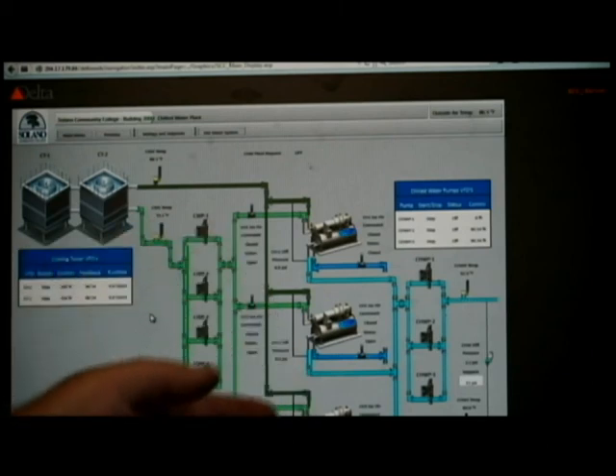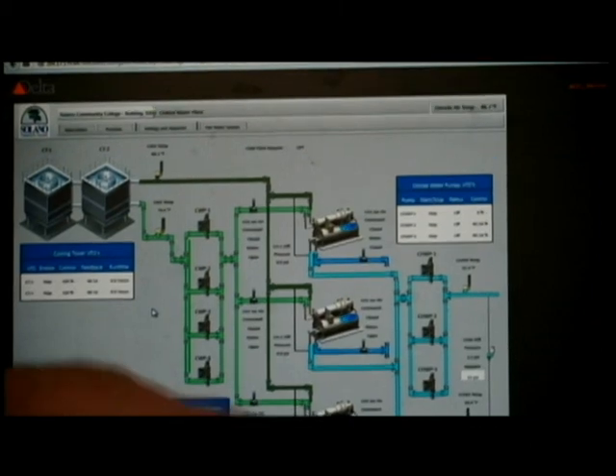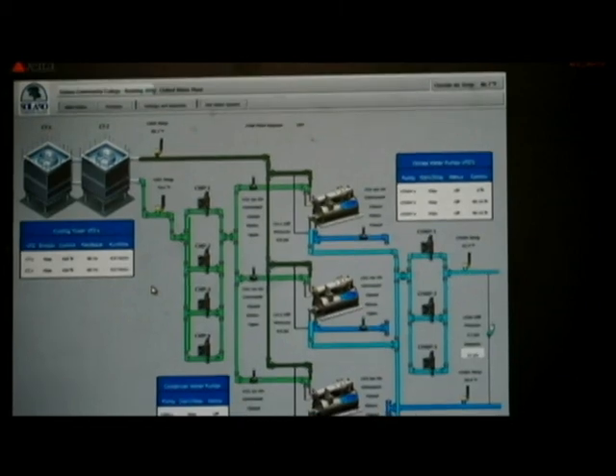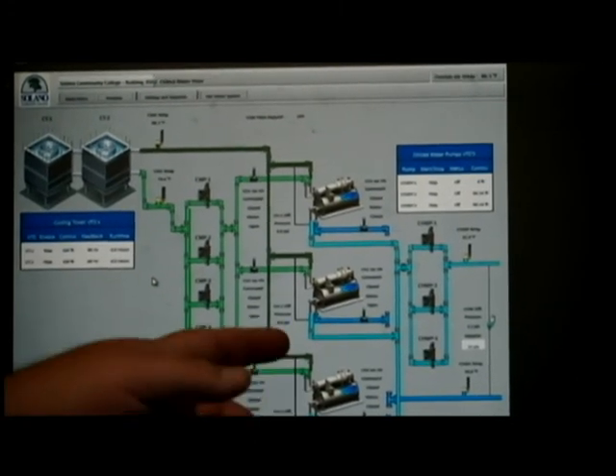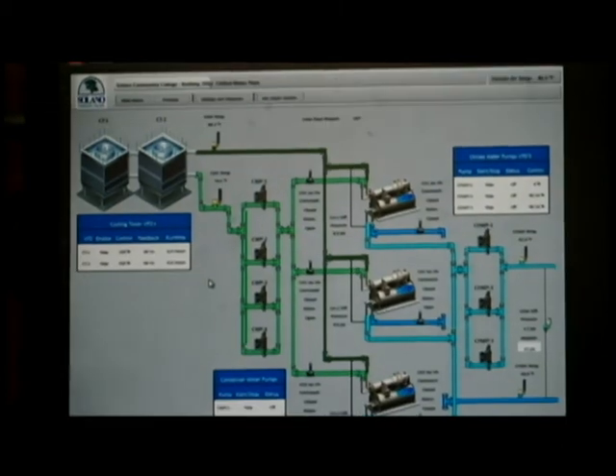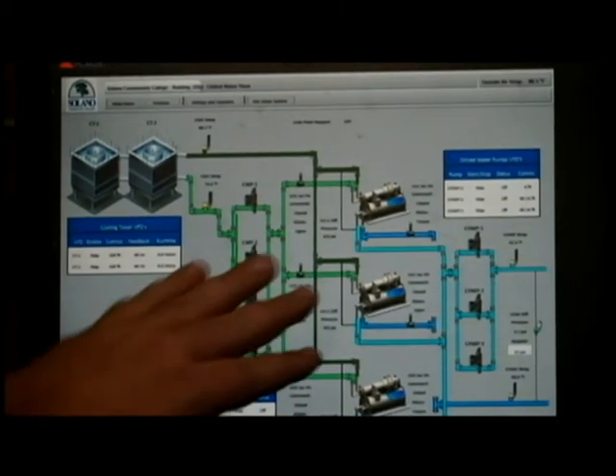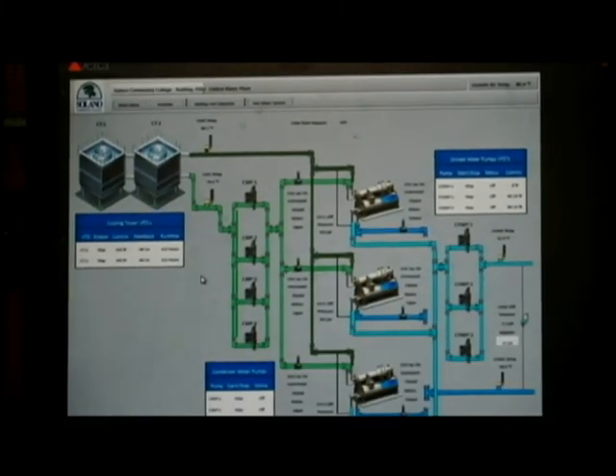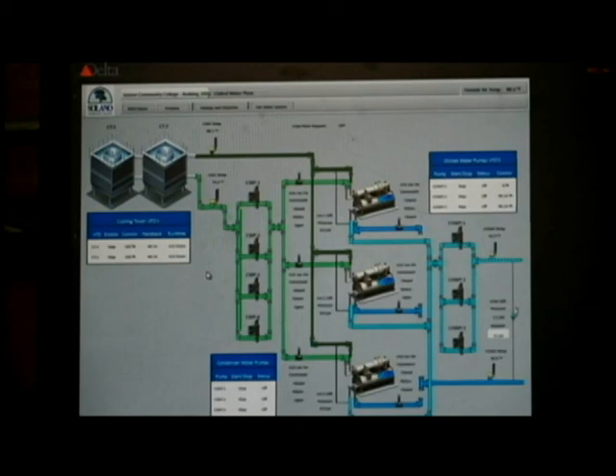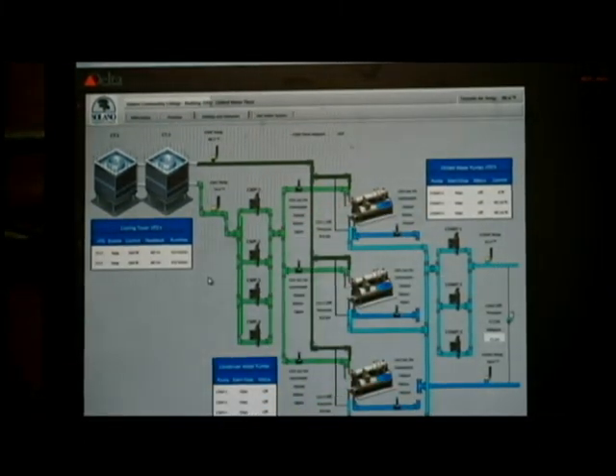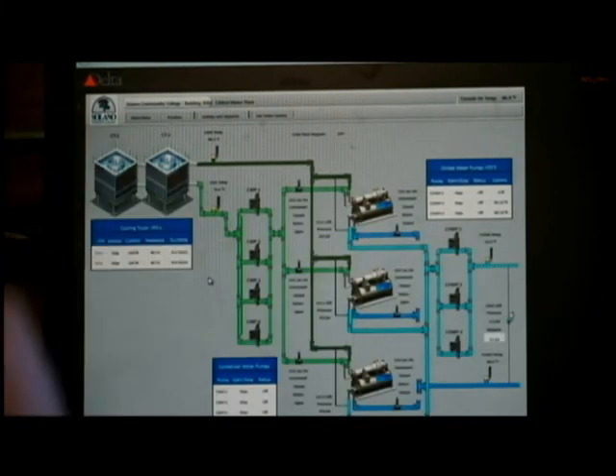Then we pass over to the chillers themselves. They can give an example of if they're running or not with the little blue flowing in there right now. They're set up to show that so you can see what it looks like if a chiller is running. And then we get to the chilled water side isolation valves on each chiller. And then out to the three chilled water pumps. And then this is where it represents being pushed out to all the buildings around the campus. And then on the return side, you have a supply and a return temperature for that as well. That lets us know what kind of differential we're getting as we get chilled water out and back in.